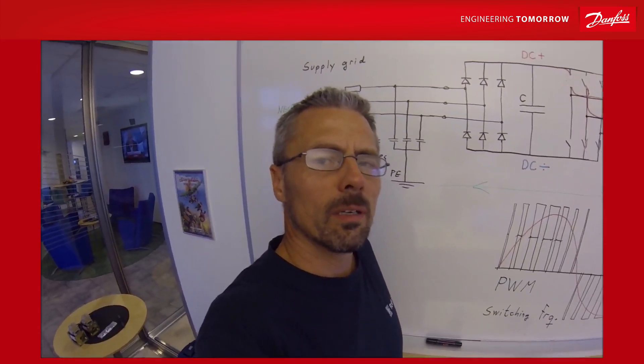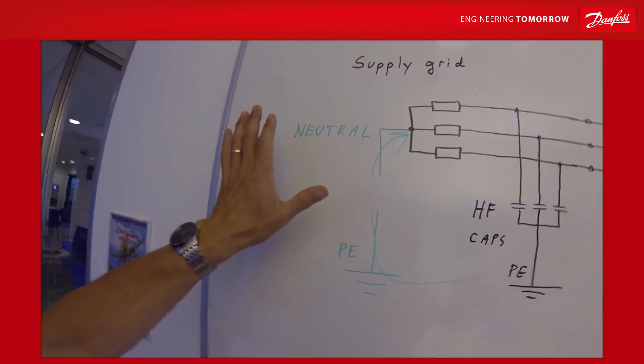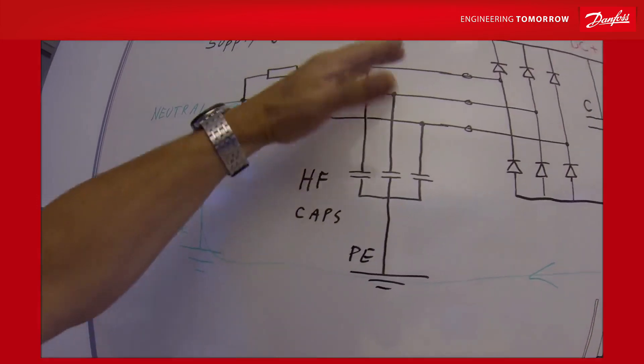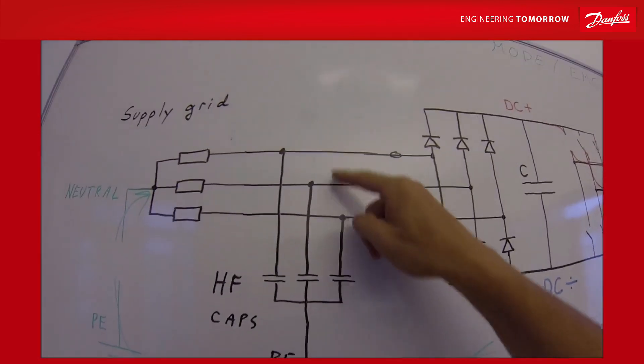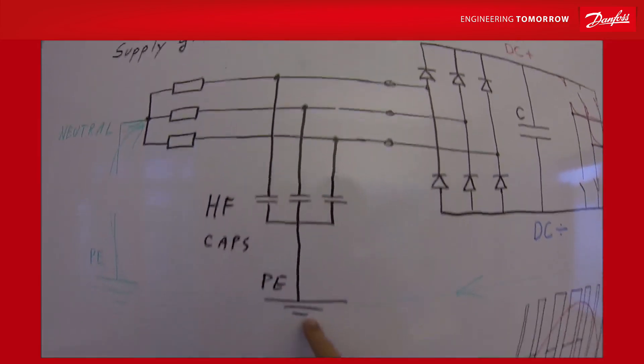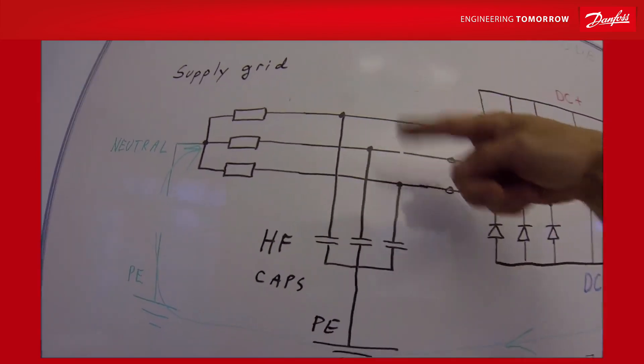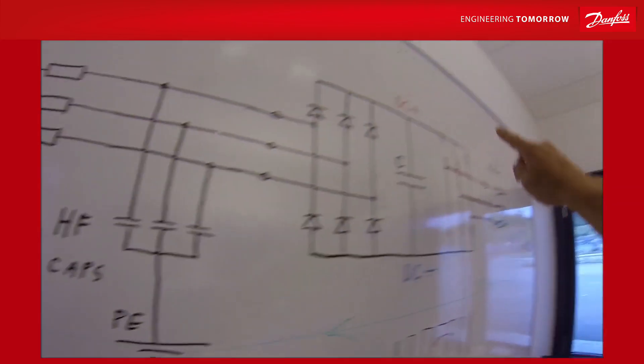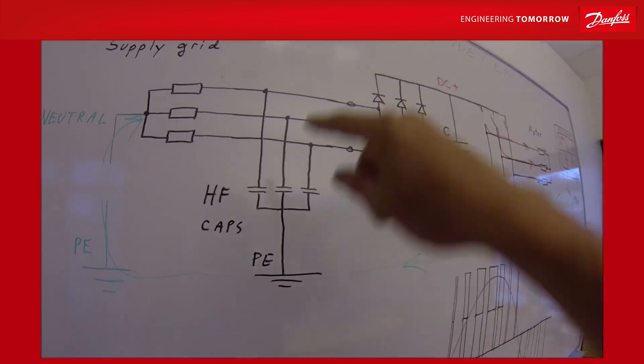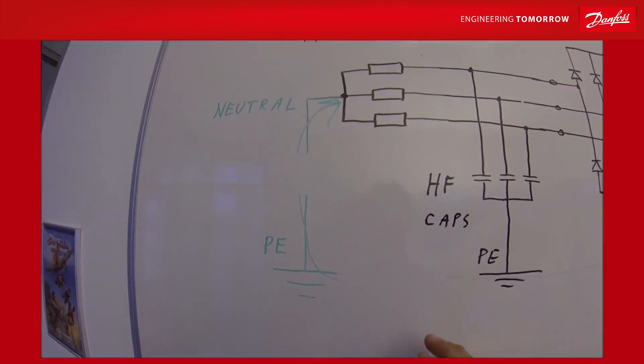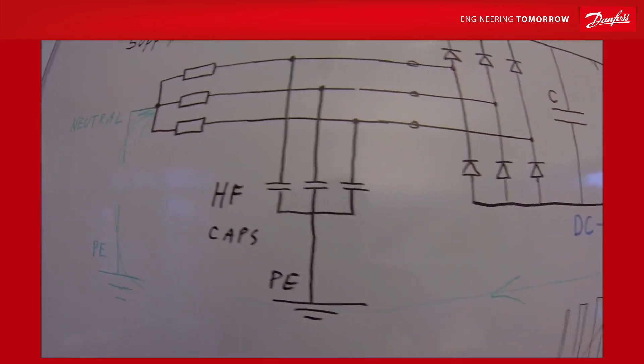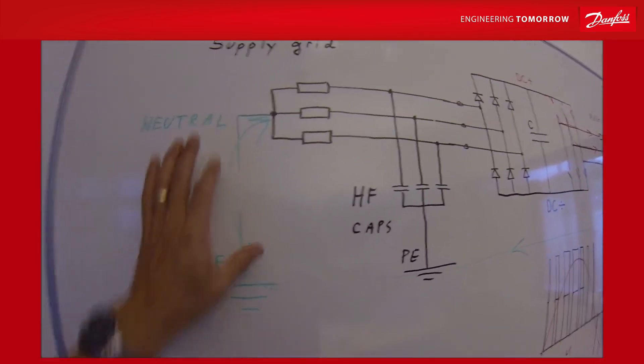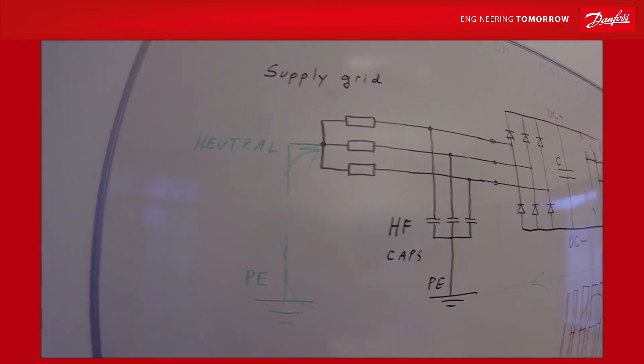One other thing that can be done to protect the supply grid from common mode is to utilize a high frequency capacitor filter. What it actually does is look at the balance between the three phases and anchor them to the protective earth. So any unbalance here will leak through the protective earth here. Basically, you create the circulating current inside this system and you avoid having the common mode distributed to your grid.